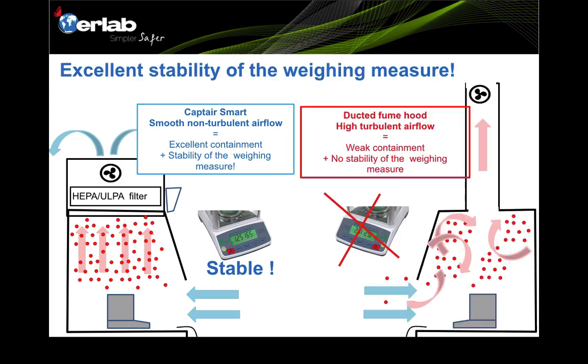Let's go into issue number two: excellent stability. The Captair Smart filtered fume hood is the best solution for weighing applications — it can be used with balances up to 6 decimal places, which is very sensitive, up to 0.001 milligram measurement accuracy. It provides excellent containment and stability during measurements. Compared with ducted fume hoods with high turbulence airflow, containment is weaker — the higher the turbulence, the greater the tendency to leak from the hood. Additionally, high airflow creates fluctuations that interfere with measurements.